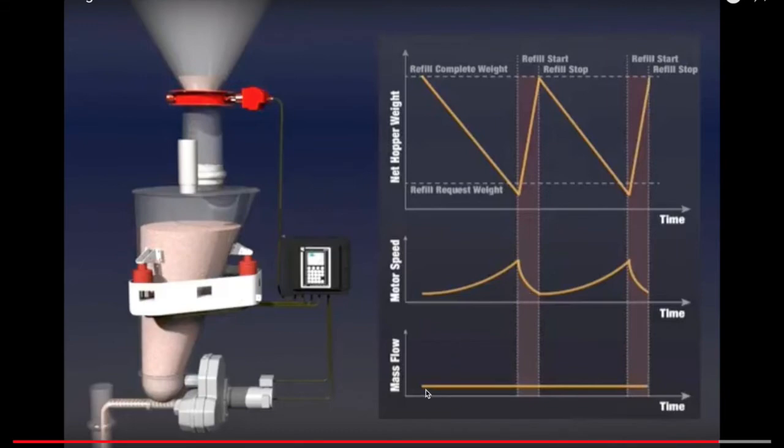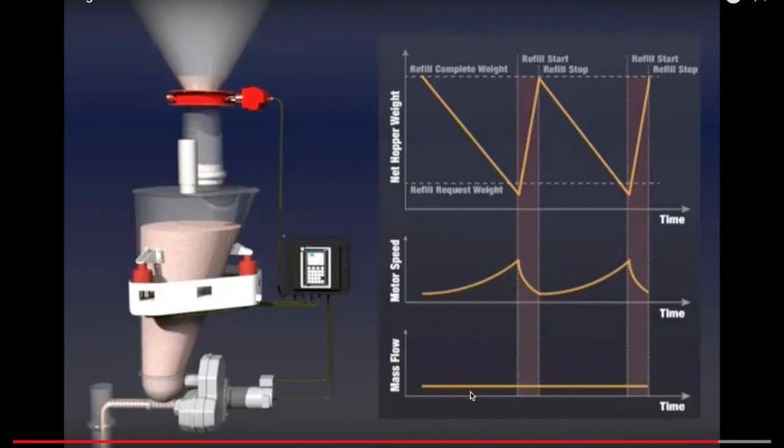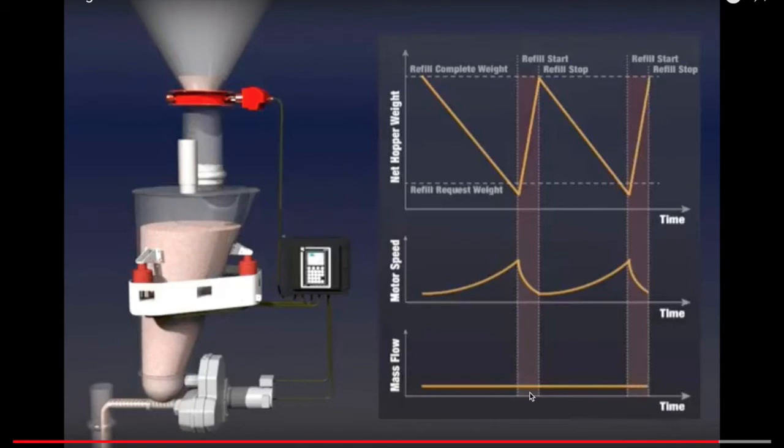And the output that the controller is sending onto the PLC is the mass flow rate. So presumably this flow rate is going to be fairly constant. So while we are in steady state, while we are in gravimetric mode, the motor speed may be increasing, but that is so that the effect is the mass flow rate is constant. And then when we are in volumetric mode, while the hopper is refilling, the motor speed does decrease as it gets more head pressure from the increase in amount of powder in the hopper, but the mass flow rate stays constant and the process repeats.